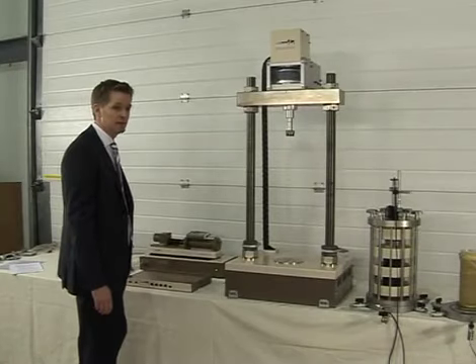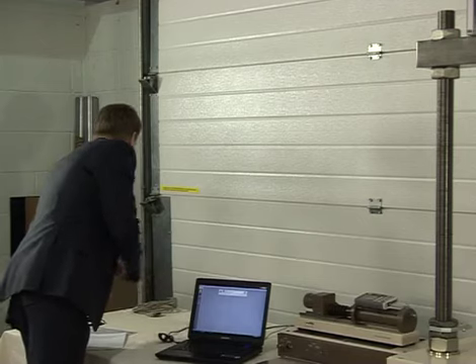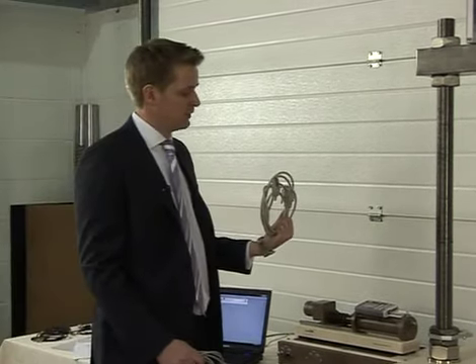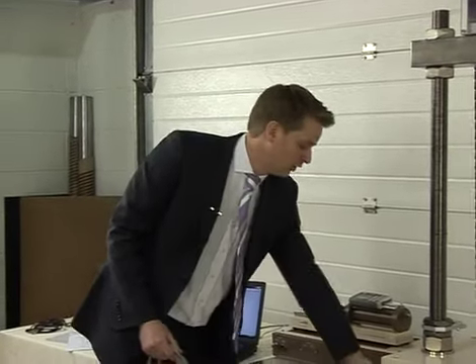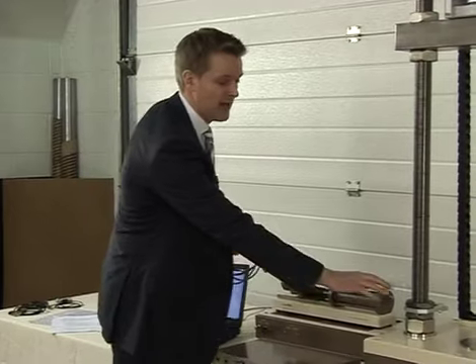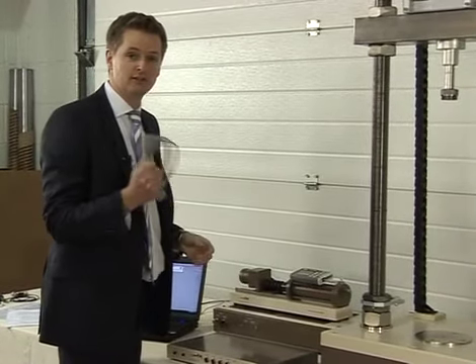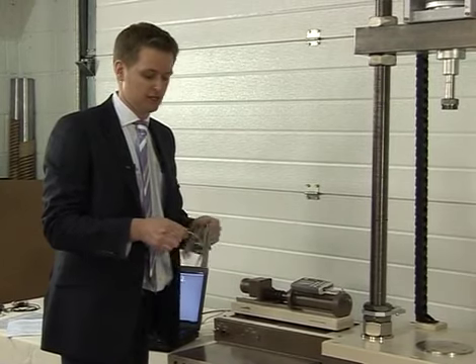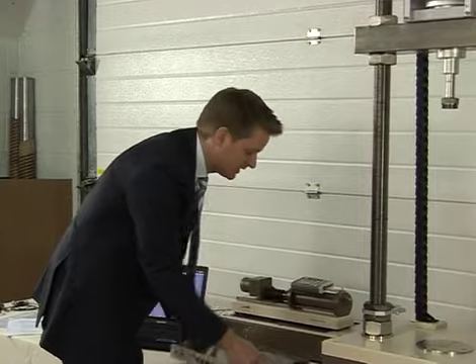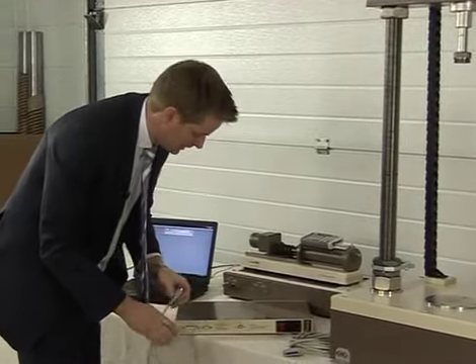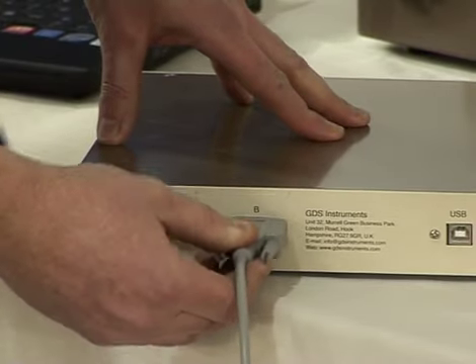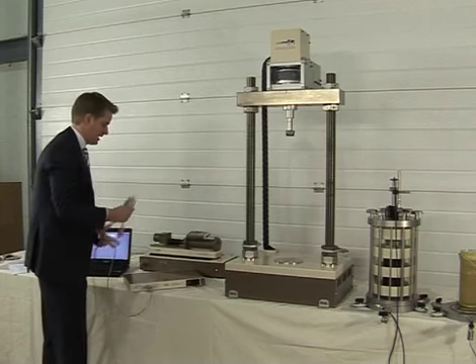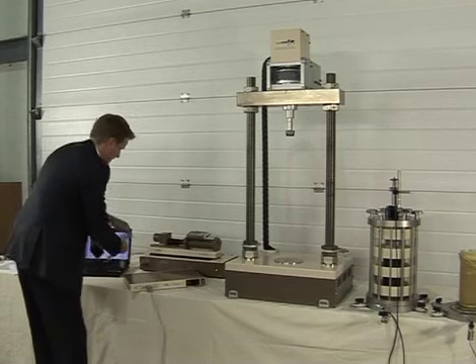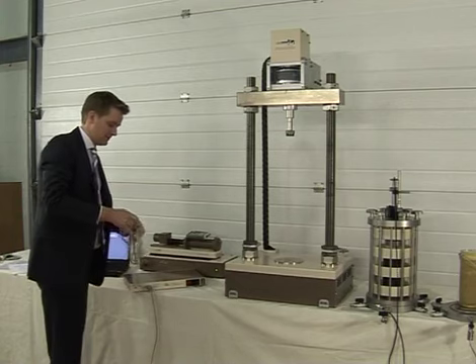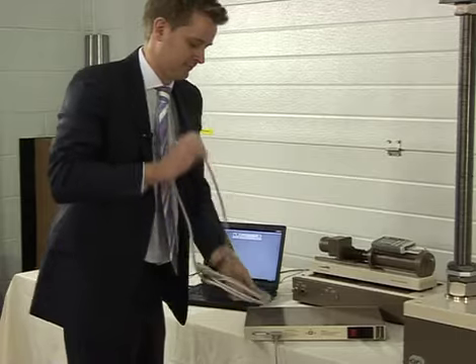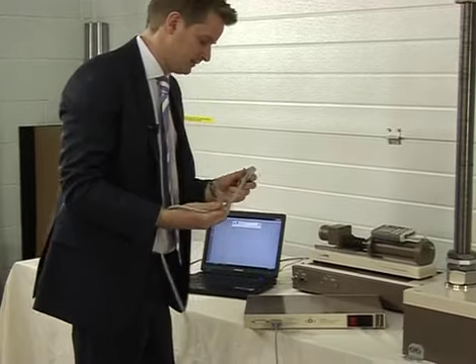So let's connect the system up and get it running. We have a 25-pin to 25-pin male to female cable for the analog signals between the DCS box and the load frame, and we have a 9-pin to 9-pin male to female digital cable. There's only one way that these cables can be connected. The 9-pin goes in the connector marked B, and the 25-pin, of course, goes in the 25-way socket marked A. Let's just get these in.